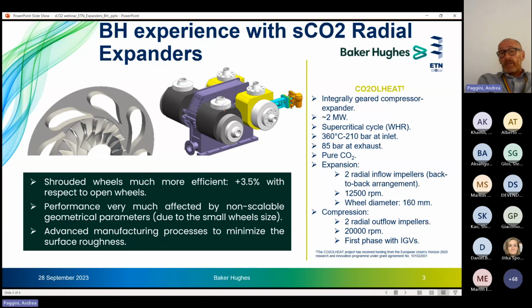Again, the integrally geared design allows to decouple the rotating speed between the expander and the compression. So, in principle, you can select the optimal rotating speed for each machine. This kind of machine, also due to the relatively small size, is pretty sensitive to non-scalable geometrical parameters, roughness, and also to a certain extent clearances. So just for roughness, it's worth mentioning that with a few 5 microns roughness, the efficiency penalty is 2.5%. So it's something which is huge.